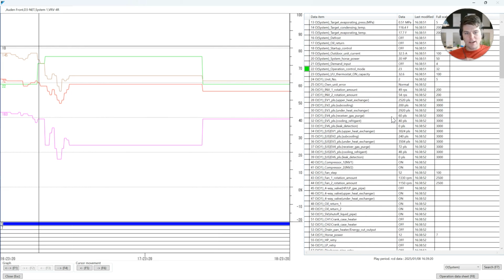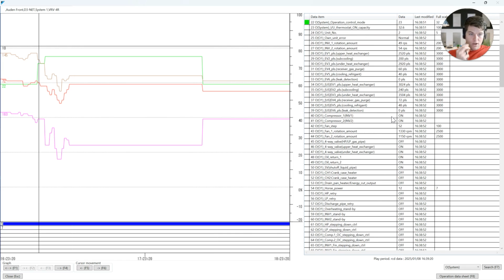This is a very quick and simple check for 2 things. One, the duration of defrost, which is very important. Extended durations are usually an issue with charge. Not saying over or under, just saying an issue with charge. Could be either. And then also, this allows me to check my four-way valves in less than 60 seconds.